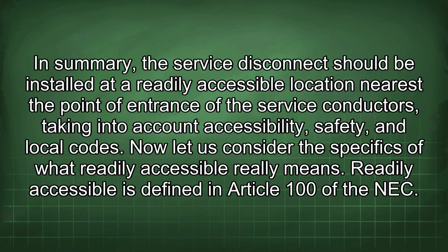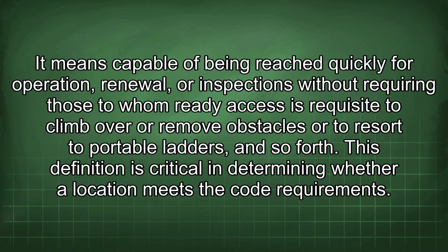Now let us consider the specifics of what readily accessible really means. Readily accessible is defined in Article 100 of the NEC. It means capable of being reached quickly for operation, renewal, or inspections without requiring those to whom ready access is requisite to climb over or remove obstacles or to resort to portable ladders, and so forth. This definition is critical in determining whether a location meets the code requirements.